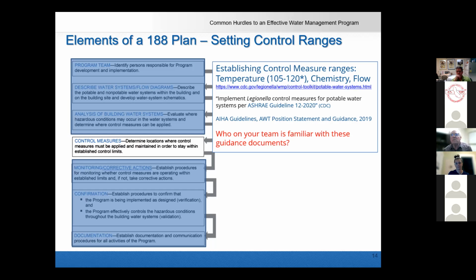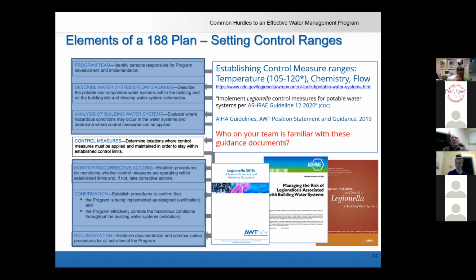So when doing that risk assessment, we first find the risk, then set those control ranges based on it. There are a few guideline documents out there — one mentioned in the Environment of Care Standard was ASHRAE Guideline 12-2020. That's also referenced on the CDC site; you can just search CDC Legionella and you'll find it easily.